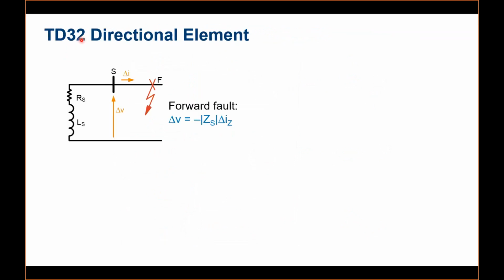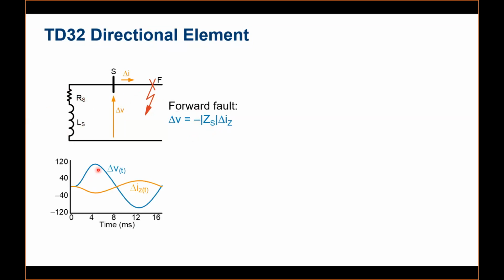For the directional decision based on the incremental quantities, just consider a fault in front of the relay. Whenever you have a fault in front of the relay, the relay will measure an impedance behind it. That is essentially the source impedance, the resistance and the inductance, and there will be a change in current in the opposite direction, or we can call this the negative polarity. So this is the principle: whenever you see a voltage that is opposite to the current, it means it's a forward fault.